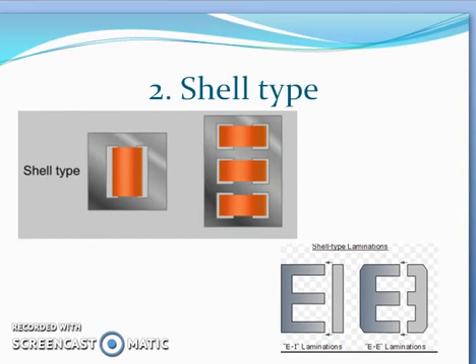In shell type transformers, the core surrounds the winding. The laminations are cut in the form of E and I. It has three limbs. The central limb carries the whole flux and side limbs carry half of the flux.